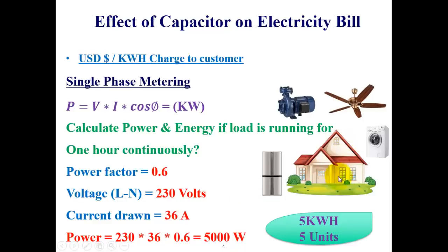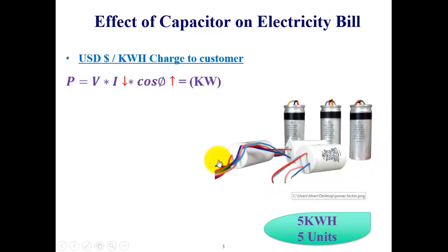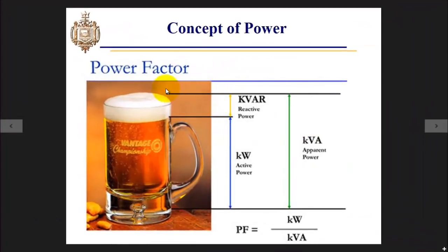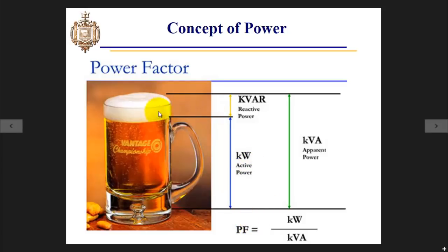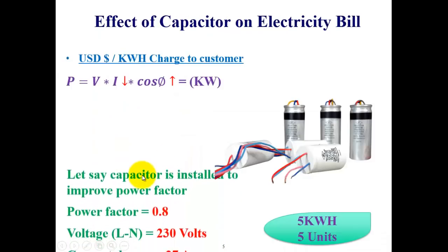Now let's connect a capacitor across the supply and see whether it reduces consumption. First, I want to clarify the concept of power factor. When you install a capacitor, the only thing it does is improve the lagging power factor. Using a wine glass analogy: the total glass represents apparent power, the wine represents active power, and the foam represents reactive power. The capacitor improves power factor by decreasing the foam and increasing the space for wine in the same glass.